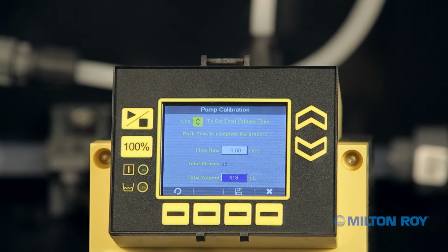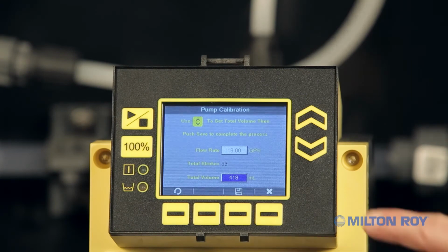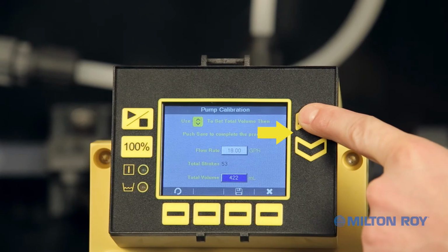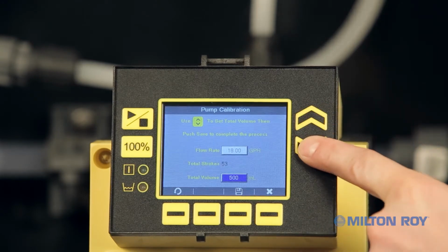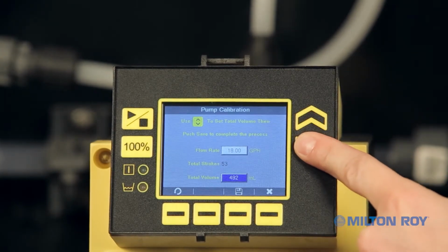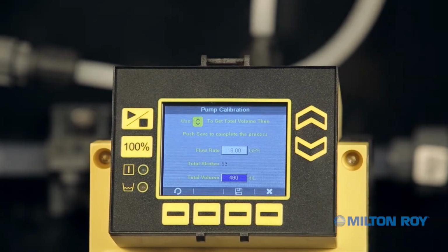We will need to adjust the total volume field area using the up-down arrow buttons on the right side of the display to match the fluid amount drawn down from the calibration cylinder. In our example, we are adjusting to 490 milliliters. At this point, we can save, restart the calibration, or cancel and exit.